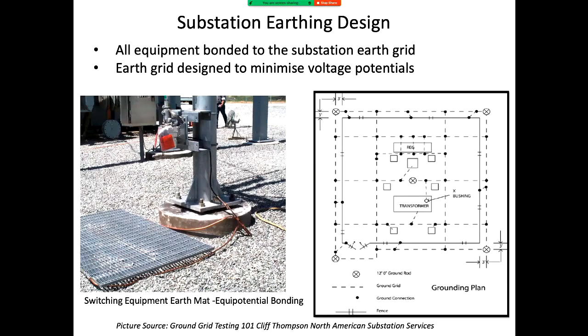Now, if there's a flash and some sort of discharge to earth, it'll run down the pole, but it'll also run down the earth conductor, since copper is much lower resistance, maybe 0.01 of an ohm versus you. So even though you're connected to it, with parallel paths, it'll bypass you. Also, you can see here things are all connected together, and that's all to do with reducing step and touch potential.